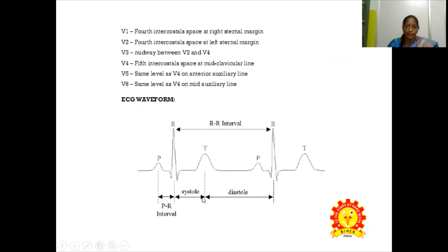Lead fault detect: the function of this block is to detect improper connection of the electrodes on the skin by continually measuring the contact resistance, and to warn the operator to make corrections by using an audible tone. Amplifier protection circuitry is also provided to protect the remaining part of the circuit from large electrical discharges resulting from the defibrillation process.